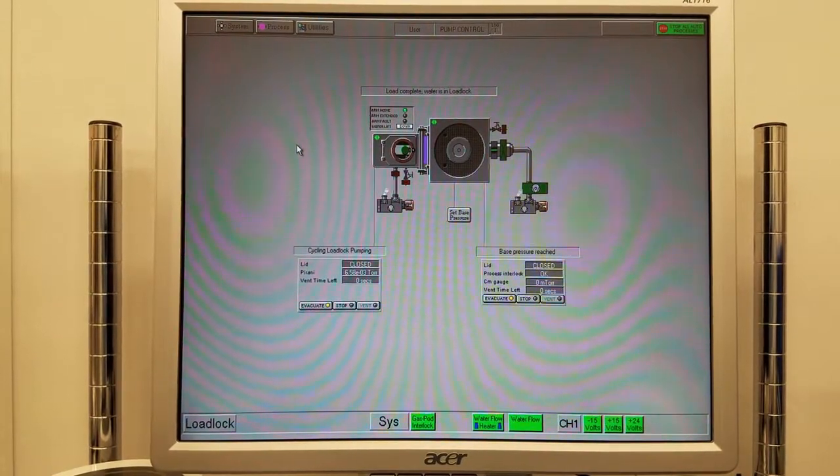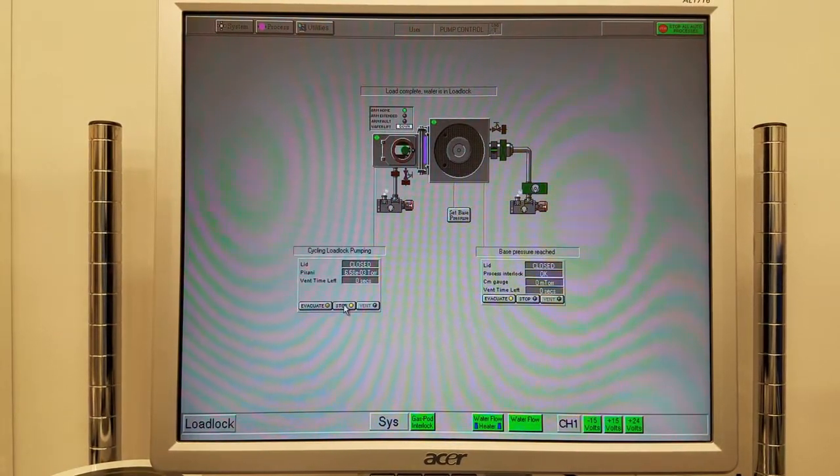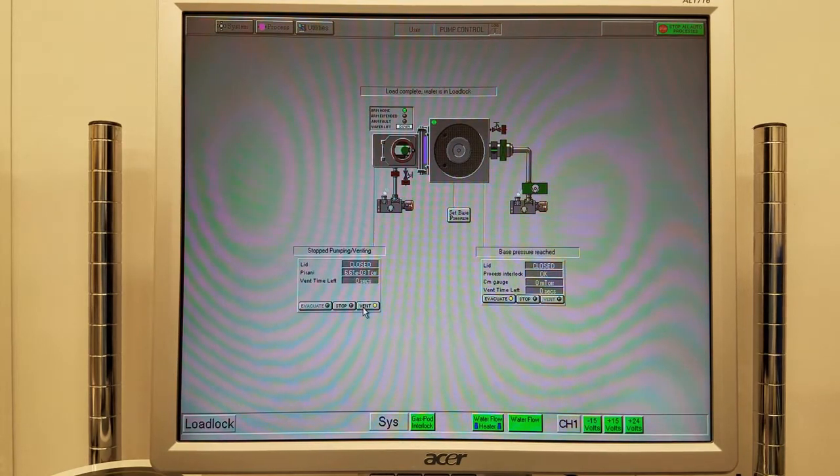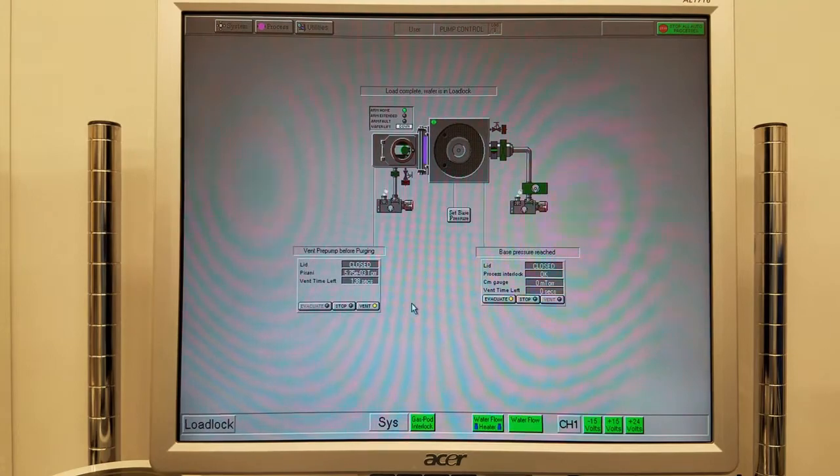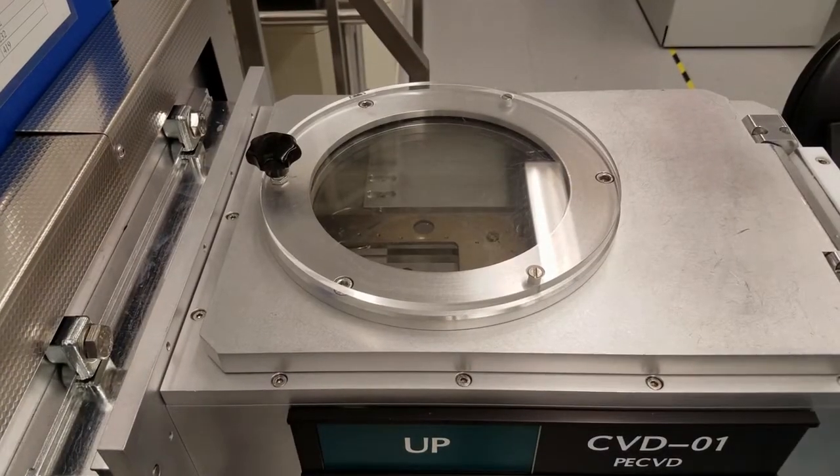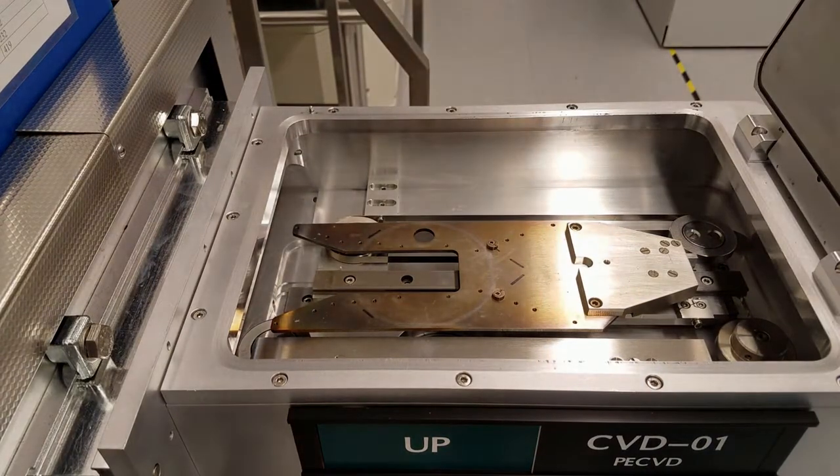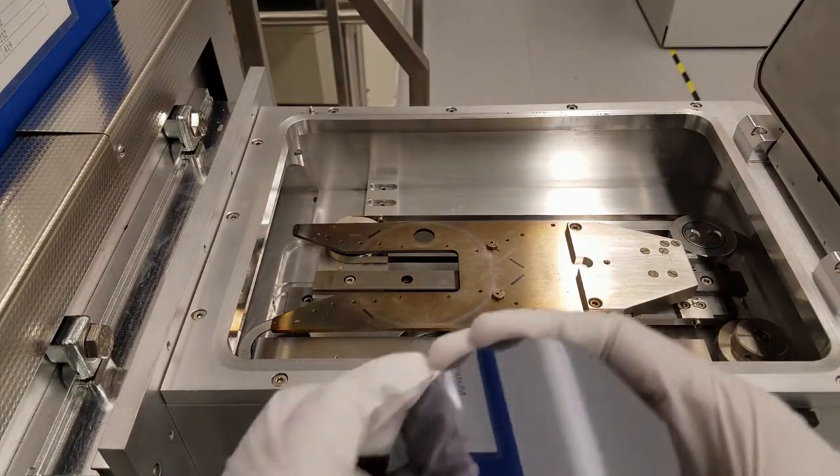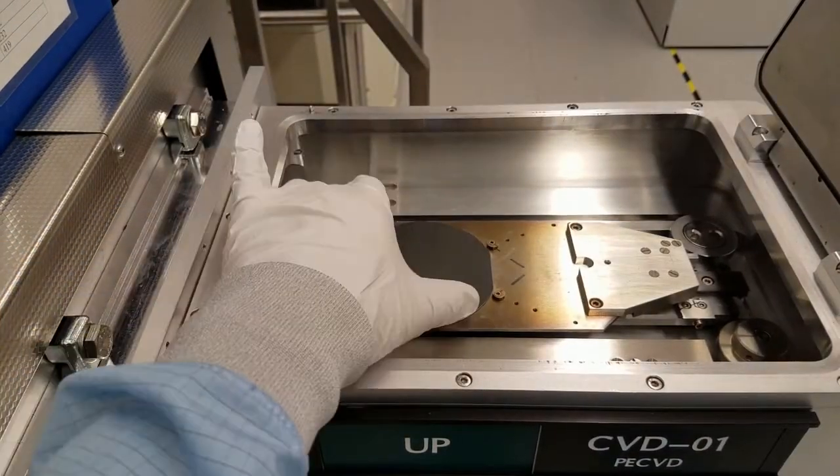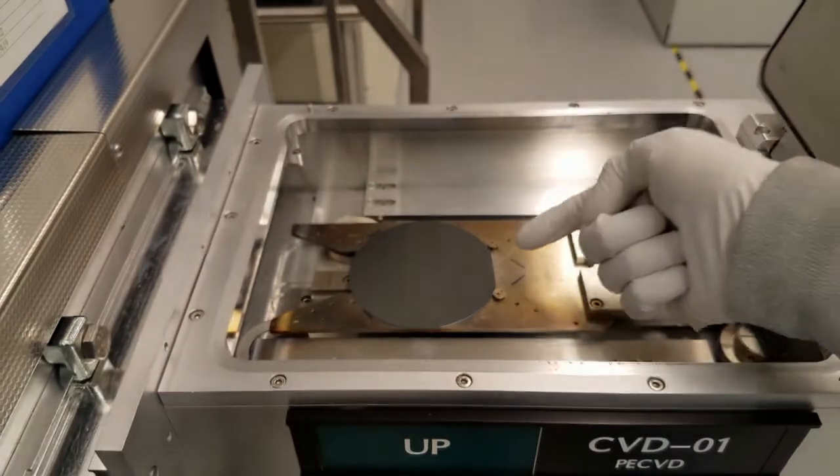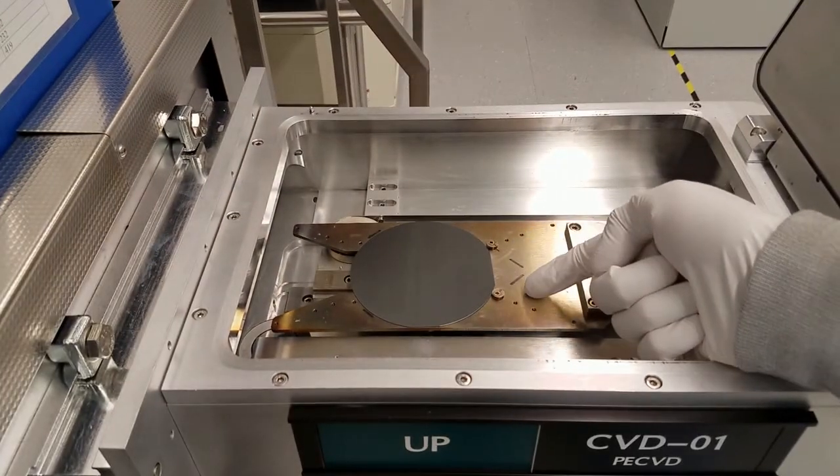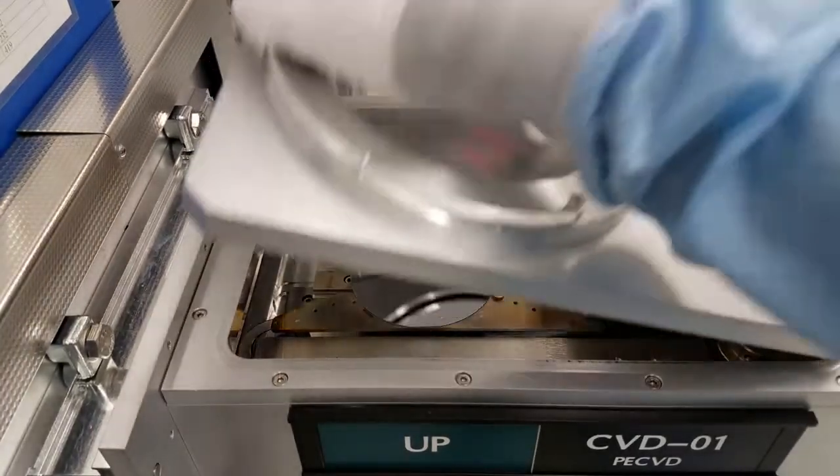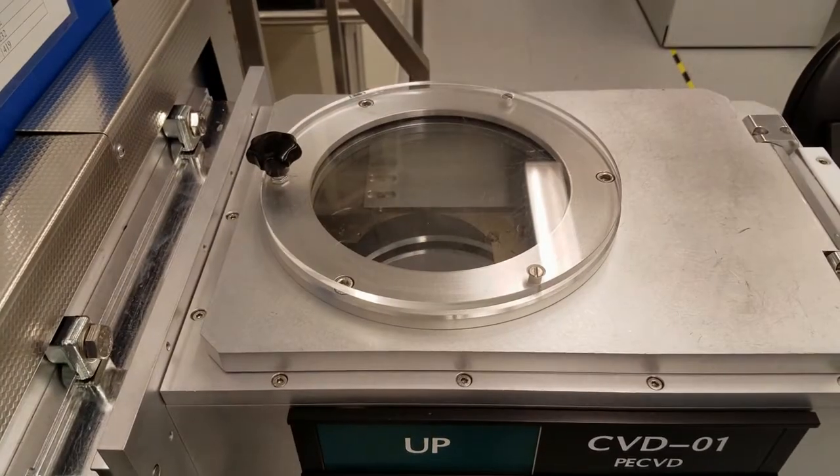Next, vent the load lock. Click stop and vent. The vent will take a couple of minutes. Once the vent is complete, you can load your sample into the load lock. Lift the lid and place the wafer on the robot arm. Line up the major flat to the two posts and close the lid.